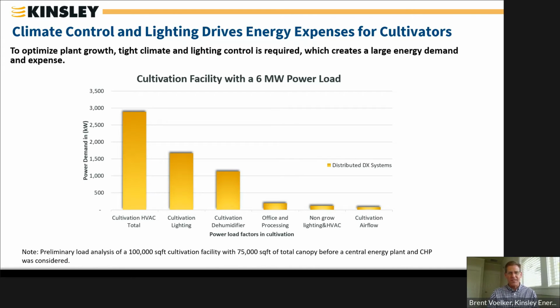This chart shows an example of a cultivation facility originally designed with a traditional HVAC system you'd be familiar with: rooftop DX units, direct expansion units that are standard HVAC, but they mostly do what we call sensible cooling, lowering temperature and making things comfortable. They're not very good at dehumidification, so you often have to add dehumidifiers to the room, which increases the load further, both the heat load and the electric load. You get a situation where your HVAC load can actually exceed your lighting load and all the other loads in the building.